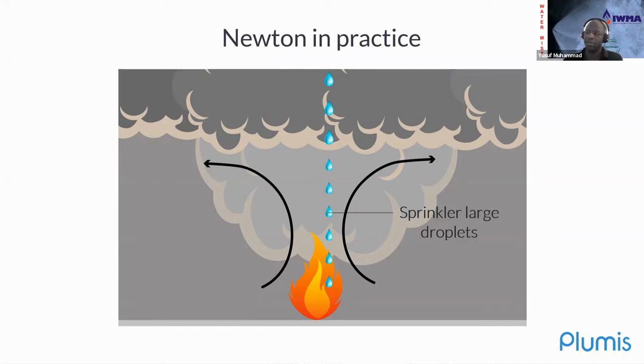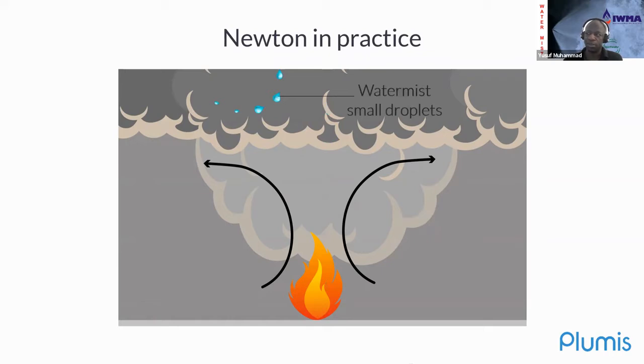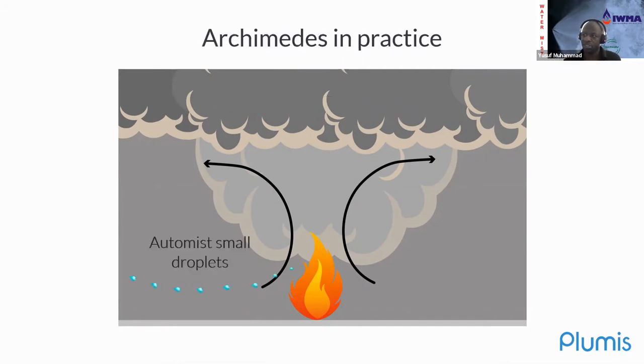Now, water mist uses a different mechanism. It uses Archimedes' principle. So one of the challenges with mounting water mist nozzles in the ceiling is that you have to cool a hot layer on the ceiling before you address the fire. Now, this is not to say that water mist nozzles from the ceiling don't work. Of course they do, but it is not as efficient because you're cooling that hot layer before you're addressing the fire. So our approach has been to find a happy medium between the floor, which is the optimum position, and the ceiling, where we get enough water mist to tumble over obstructions, but we can still ensure that there's a significant amount of water mist in and around the base of the fire.